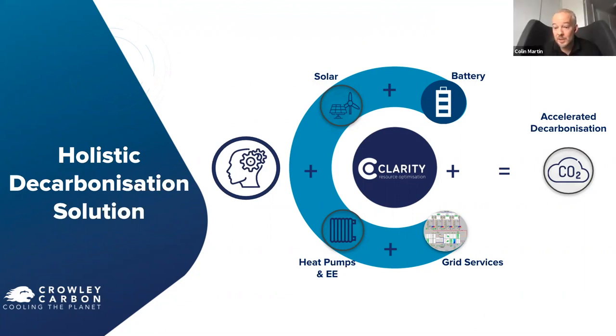If you have a steam requirement, this is where a good bit of analysis needs to be undertaken. A lot of people may have 10 bar steam but actually step it down to 2 bar, and the use is down at that lower level - that would need to be established. But if there's an absolute requirement for 8 bar and certain temperature levels, you're not going to heat pump concentrate that up. That's where the electric boiler would come in, taking that portion of the steam demand as part of a holistic solution.